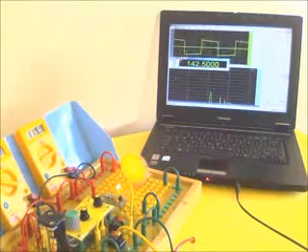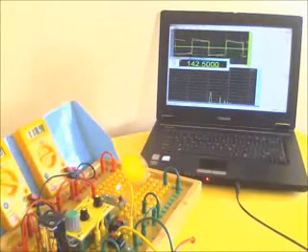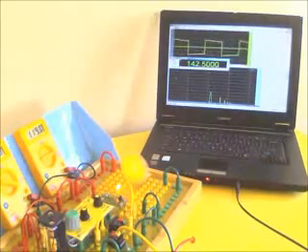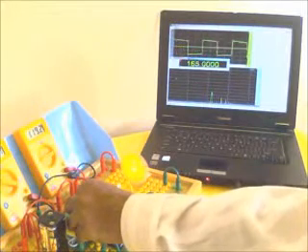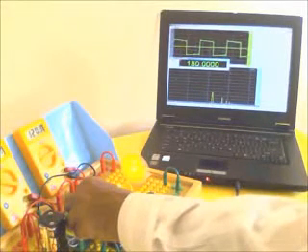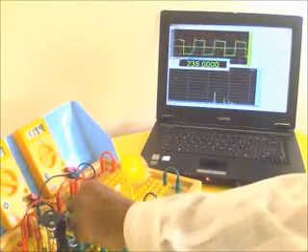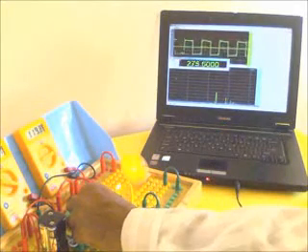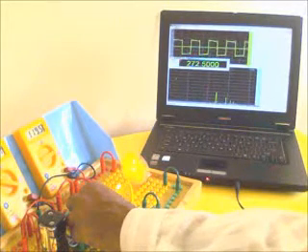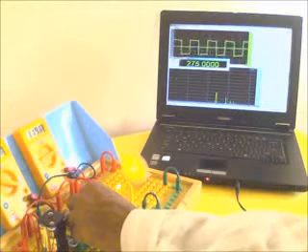Now we are able to see the frequency and at the same time the fan leaves. Now adjust the frequency. The frequency now shows 142 Hz. Increase it. See the fan motor leaves. Doesn't stop visually. Yes, now it is visually stable. Even though the fan leaf is running at a high speed, the fan leaves are visible.